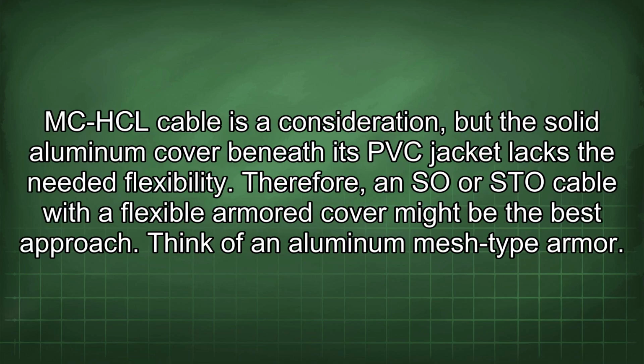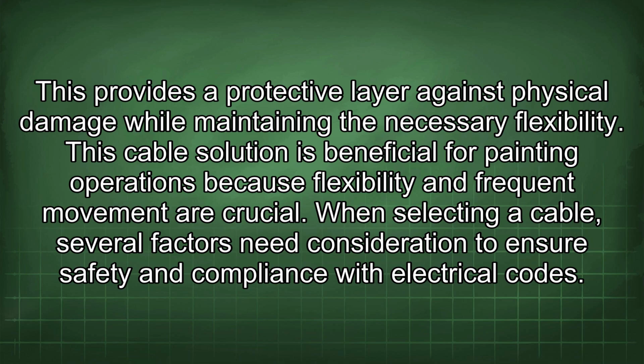MC-HCL cable is a consideration, but the solid aluminum cover beneath its PVC jacket lacks the needed flexibility. Therefore, an SO or STO cable with a flexible armored cover might be the best approach. Think of an aluminum mesh type armor. This provides a protective layer against physical damage while maintaining the necessary flexibility. This cable solution is beneficial for painting operations because flexibility and frequent movement are crucial.